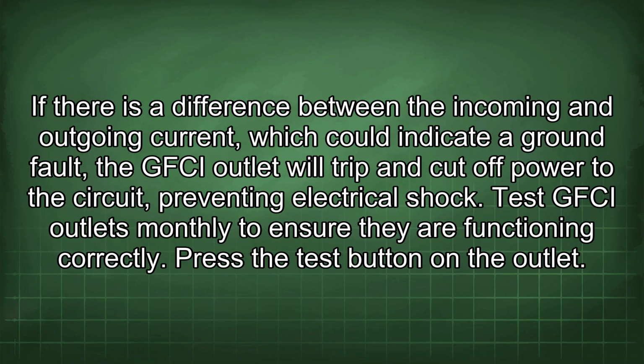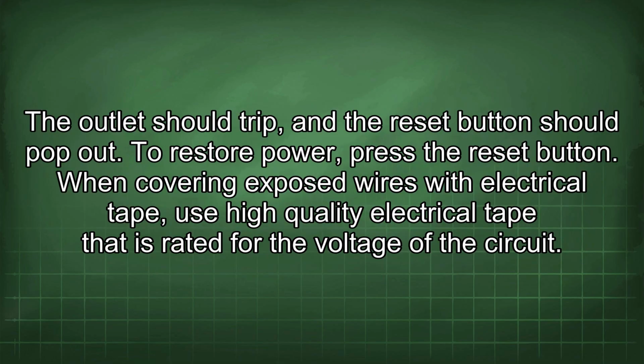Test GFCI outlets monthly to ensure they are functioning correctly. Press the test button on the outlet. The outlet should trip and the reset button should pop out. To restore power, press the reset button.